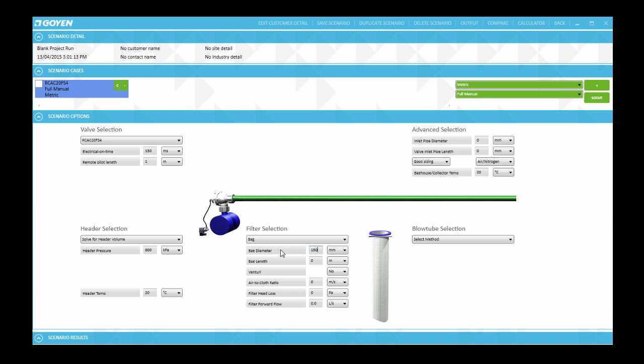The next parameter that will need to be specified is the bag length. A typical length that we will use in this case is 6 meters. Other bag lengths of maybe shorter length or longer length up to about 10 meters or even maybe 12 meters can be used.